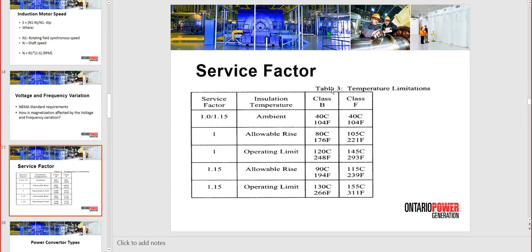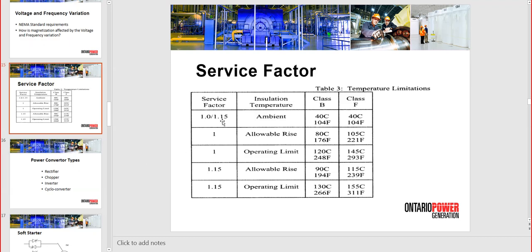Service factor, you hear that very much in different applications. As we said, we have class F. Service factor is usually 1, so 1 says that it doesn't accept overload. However, in some applications you can order the motor higher than 1, 1.15, even 1.25. What that means, simply, is that North American standards allow for a 15% or 25% overload without damaging the motor. For a 10 minute overload, 15% is still going to work fine. It's like a little bit of an oversize of the motor, so that's all this service factor is.